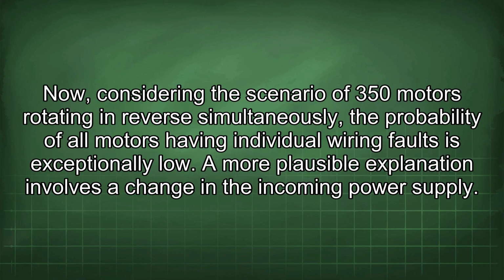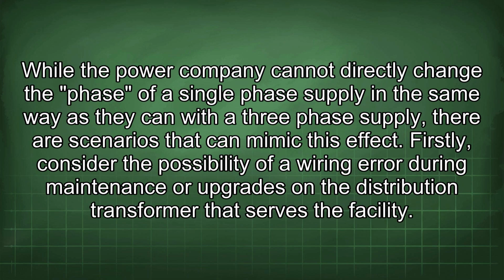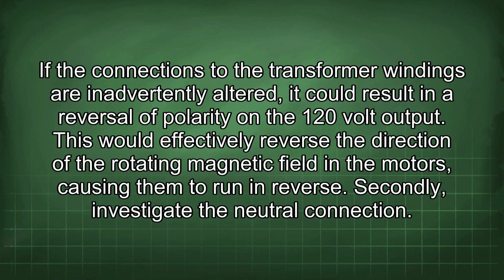Now, considering the scenario of 350 motors rotating in reverse simultaneously, the probability of all motors having individual wiring faults is exceptionally low. A more plausible explanation involves a change in the incoming power supply. While the power company cannot directly change the phase of a single-phase supply in the same way as they can with a three-phase supply, there are scenarios that can mimic this effect. Firstly, consider the possibility of a wiring error during maintenance or upgrades on the distribution transformer that serves the facility. If the connections to the transformer windings are inadvertently altered, it could result in a reversal of polarity on the 120-volt output. This would effectively reverse the direction of the rotating magnetic field in the motors, causing them to run in reverse.